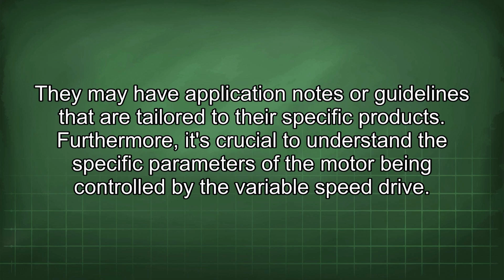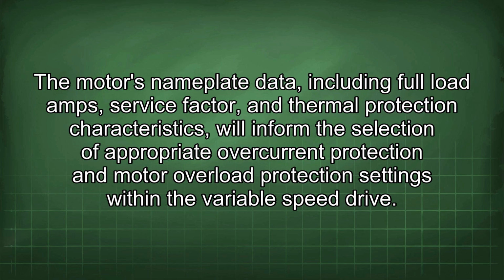Furthermore, it's crucial to understand the specific parameters of the motor being controlled by the variable speed drive. The motor's nameplate data, including full load amps, service factor, and thermal protection characteristics, will inform the selection of appropriate overcurrent protection and motor overload protection settings within the variable speed drive.